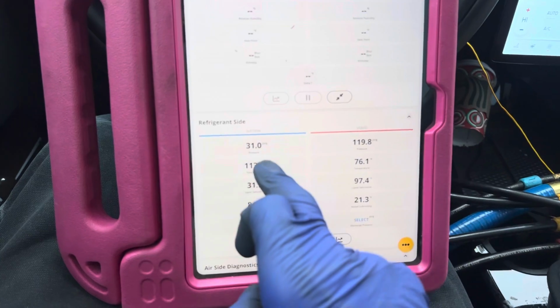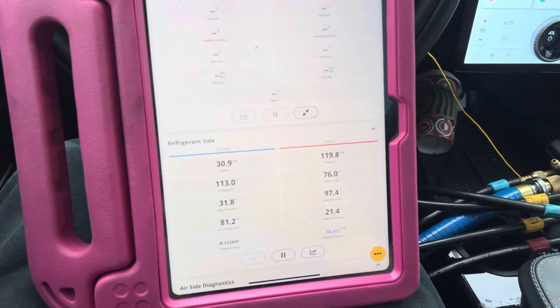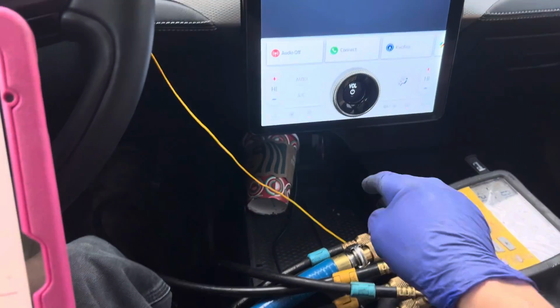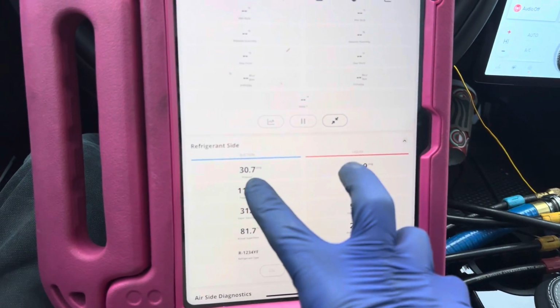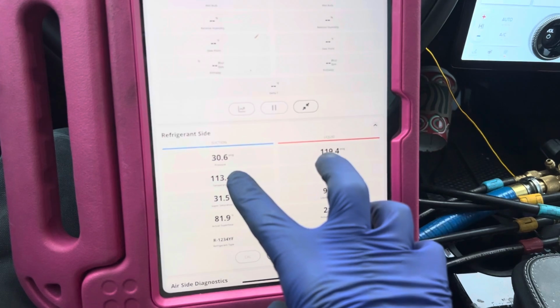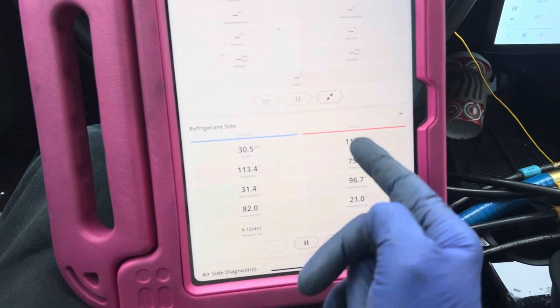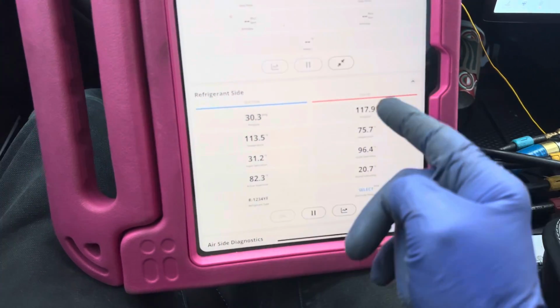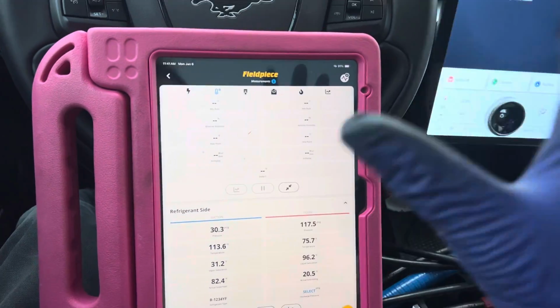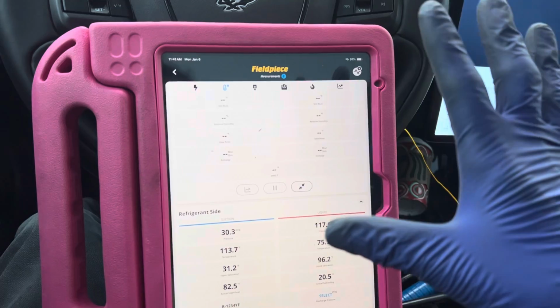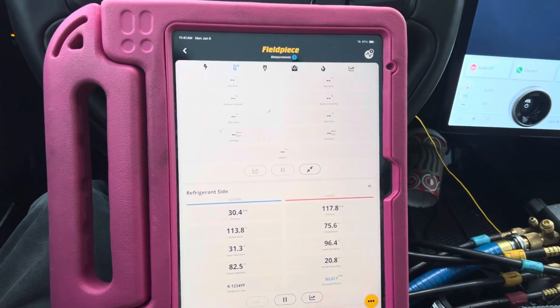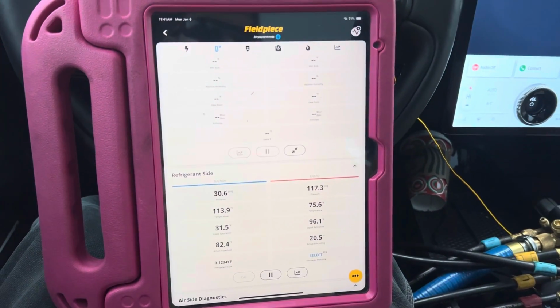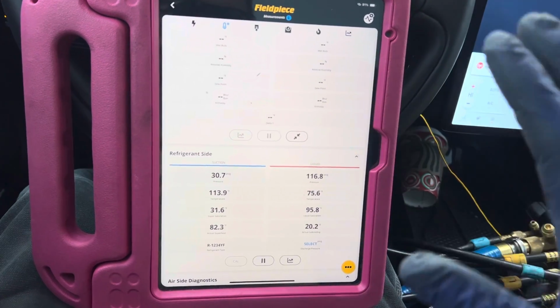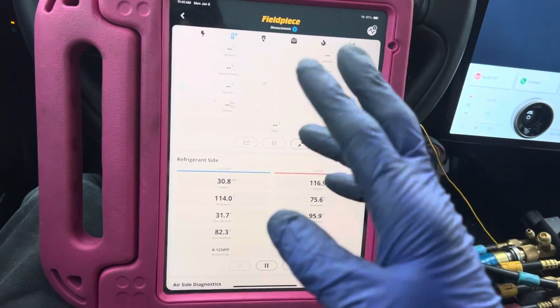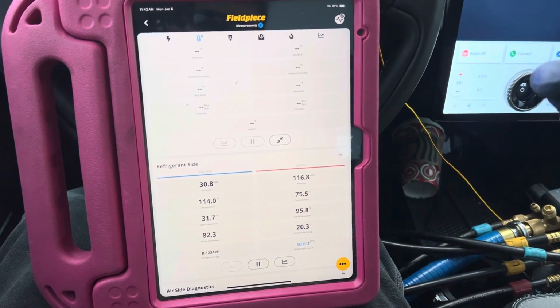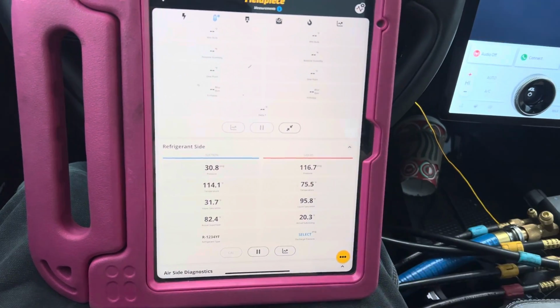So let's look at this right now. There's our pressures outside. I have it on max high temperature right now. And on some other vehicles, you'll see the high side and low side flip. The ones that actually switch the gas flow to the evaporator, you'll see them flip, and then this would become like 120 or 140 psi, and this one will become 30 or 20 psi on this side. It all depends on year, make, model, vehicle, the manufacturer. This is the Wild West. It's a complete mess out there in the way they're handling heat pumps in the automotive industry. There are no really nice standards like usually in the residential. There are some funny things in the residential. There are two expansion valve systems out in the condenser. There are some that put one indoors and one outdoors. There are a few different ways, but automotive is really messed up.